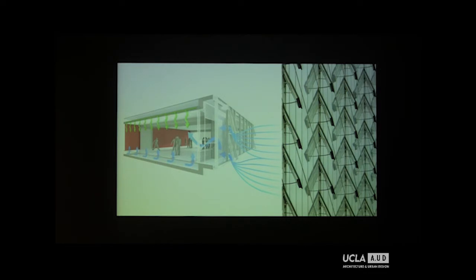Last year they operated this building almost 40% of the time in natural ventilation mode. When they go into natural ventilation mode, they turn off all mechanical systems, so there's no air coming from the raised floor.